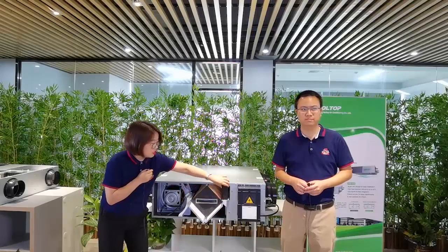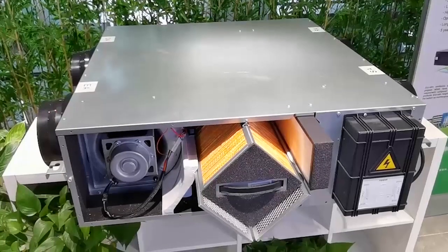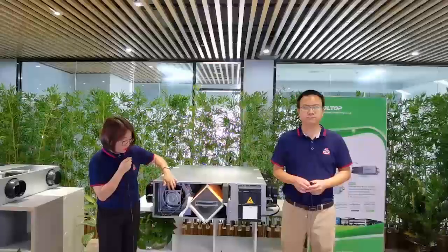The model I will show you is a 600 cubic meter per hour model. For bigger airflow from 500 to 2600 cubic meter per hour, the design and structure is a little different. We can see the access door is at the side. There's a regular access door for maintenance of the primary filter, the PM2.5 filter, and the heat exchangers. We increased two more access doors for the fan motor and the control, making it easier for maintenance.